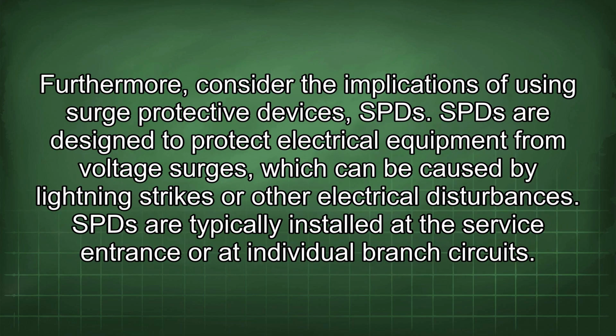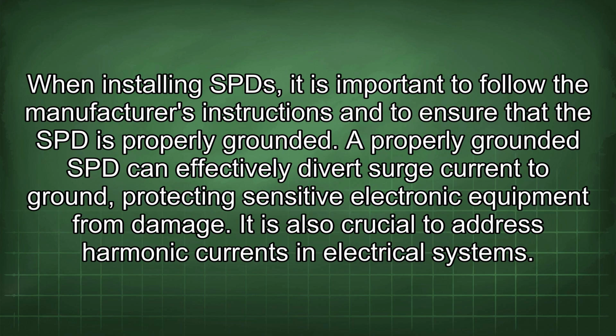Furthermore, consider the implications of using surge protective devices, SPDs. SPDs are designed to protect electrical equipment from voltage surges, which can be caused by lightning strikes or other electrical disturbances. SPDs are typically installed at the service entrance or at individual branch circuits. When installing SPDs, it is important to follow the manufacturer's instructions and to ensure that the SPD is properly grounded. A properly grounded SPD can effectively divert surge current to ground, protecting sensitive electronic equipment from damage.